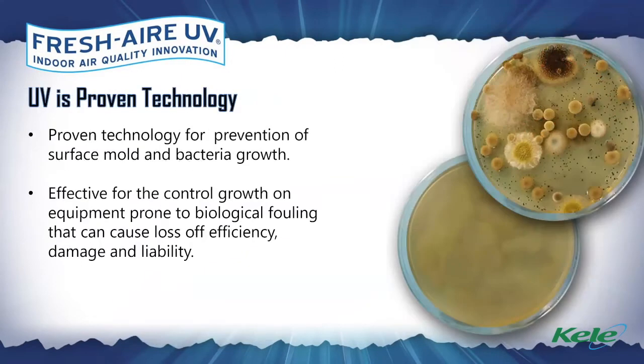Now, this is a test I've done hundreds of times, and it's a great indicator of what's happening inside the air handling unit. Quite often I'm lucky enough to meet with facilities and healthcare providers, and I'm often brought in to meet with the director of facilities, who in turn will bring me to their air handling unit to take a look. And they're typically very proud of the nature and the condition of their HVAC unit itself. And for this conversation, we'll call him Mark. Now, Mark brings me into the air handling unit. We take a look, and it looks clean. But I explain that what we're obviously looking at is either the leaving or leading edge of the air conditioning coil, and that maybe makes up 5% or less of the actual surface area of the coil itself. The surface area is tens and tens of thousands of square feet. And we obviously do not see that. That's inside that coil section.